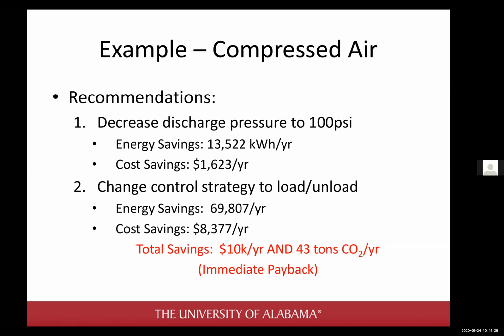The second thing, which was really neat, is that they had a control on this compressor that you could literally go up to the control panel and poke around a little bit and change the control strategy from modulation, which is actually very good because it maintains an incredibly steady pressure by this butterfly valve. We changed it from modulation to load unload. And a load unload strategy, I'll go back to this, has this line right here, this little red line.